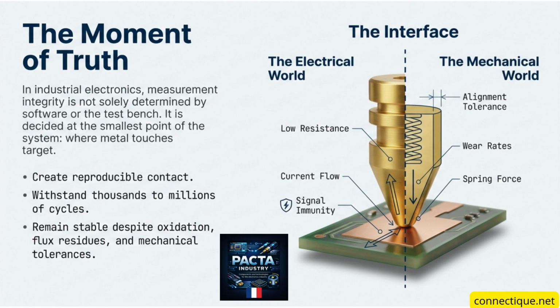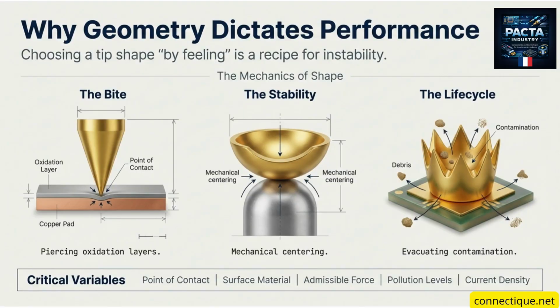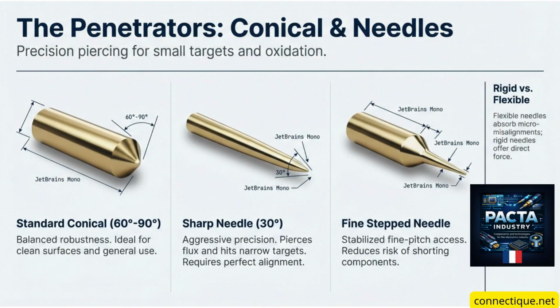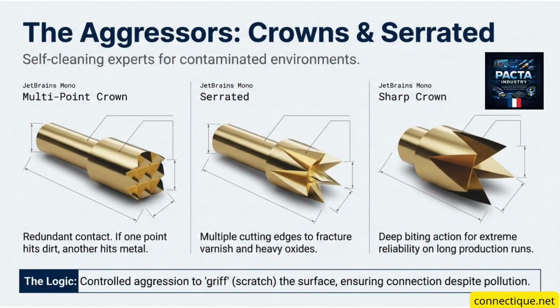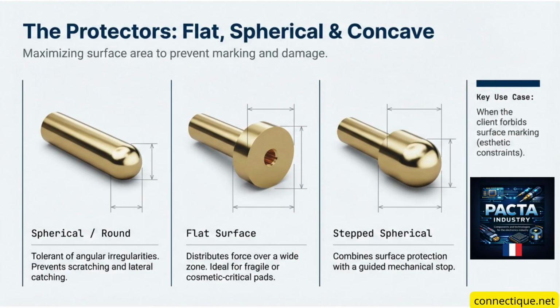Well, a 30-degree point of copper or steel, it's going to be fragile. Extremely fragile. That's the trade-off. It wears out fast. It dulls. And worse, it can bend. If it hits the surface at a slight angle, if your machine isn't perfectly aligned, that tip acts like a lever and just snaps. So it's the glass cannon of probe tips. That's a perfect way to put it.